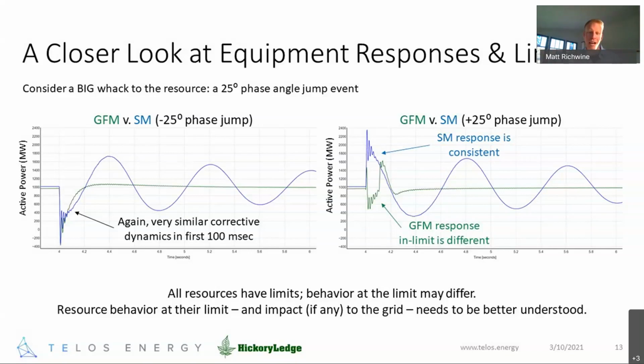However, on the grid forming side, where you have power electronics in between, what you can see, and what we know and expect, is that at some point they're going to hit a limit. All resources have limits, so this is not unexpected, but the behavior at the limit may vary, particularly when it's software defined. So what we wanted to show is that, in general, we're seeing very promising aspects from grid forming technology, but we don't want to paint too rosy a picture, there is a lot more we need to understand, particularly the behavior at the limit. Not because we intend to operate at or over the limit, but because it's important to know what happens when you get there, such that the results are acceptable and you don't have a massive failure. This is one of the things we wanted to share that we're still digging into and that needs to be better understood.